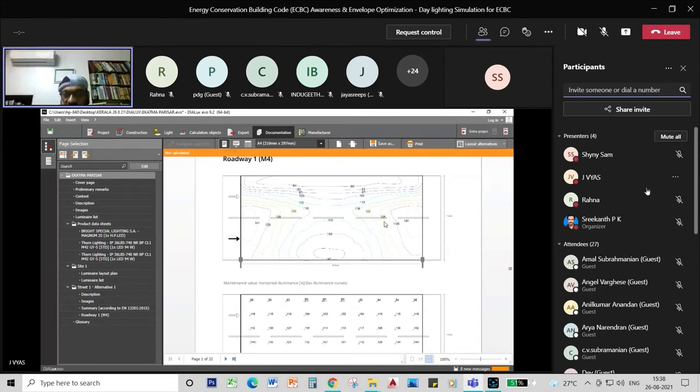This is more intense, this is dispersing, and these are affected from both sides. So this is lux level 103, 135, 141. The minimum should be 100 lux on the road. So 110, 110, 97, at the distant edge it is 90, marginally a little lesser.